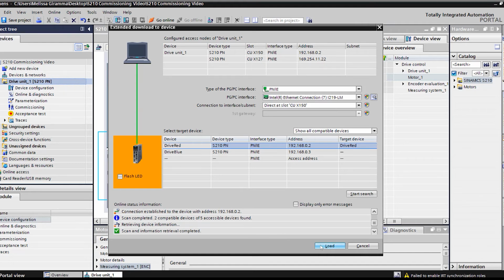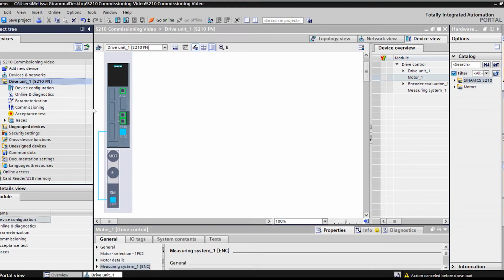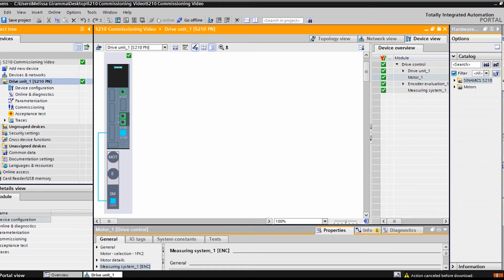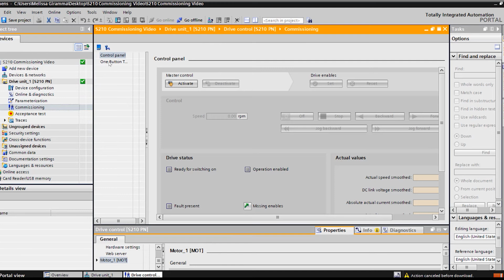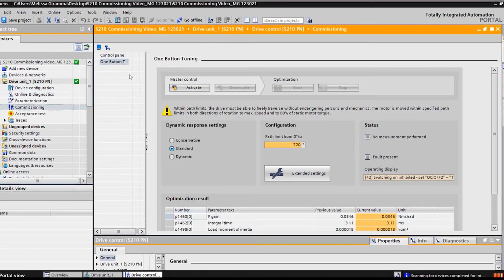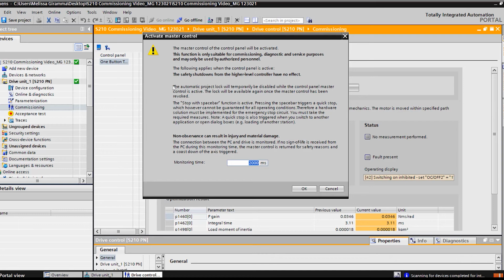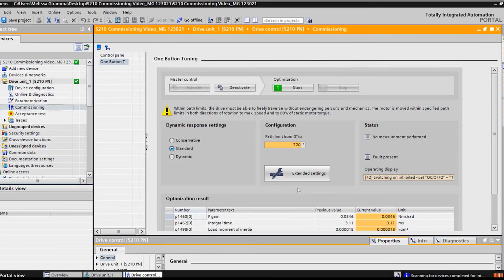Once the download completes, select Go Online and confirm that an orange bar appears. Under the S210 drop-down menu, select Commissioning and then One Button Tune. Click on Activate Control and a notice will appear that our actions will be canceled if the PC and S210 lose connection for too long. Select OK. Enter how many degrees the motor shaft can turn during the tune and select Start. During the tune, you will see the motor shaft spin at different speeds and directions until complete.